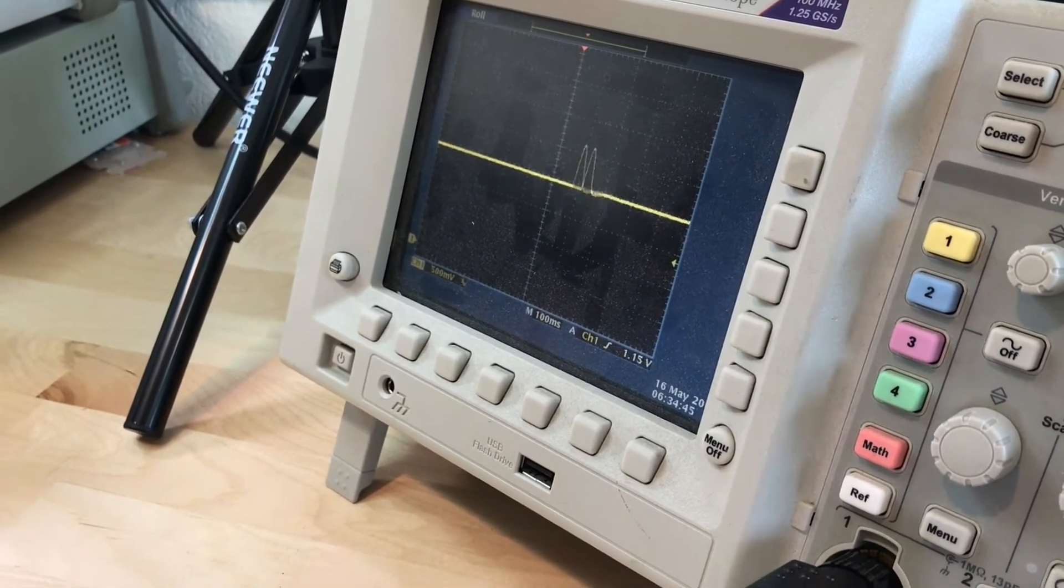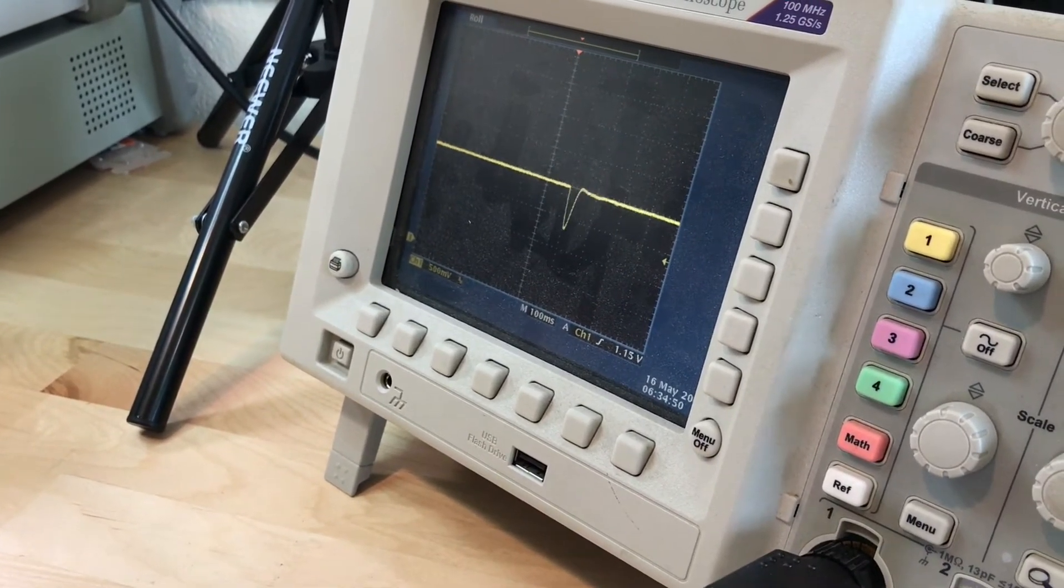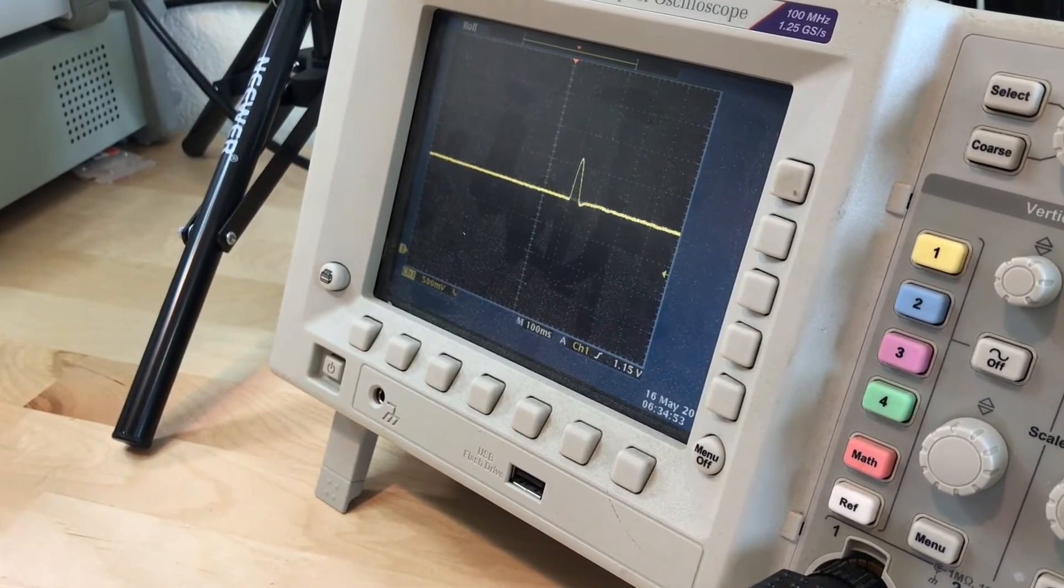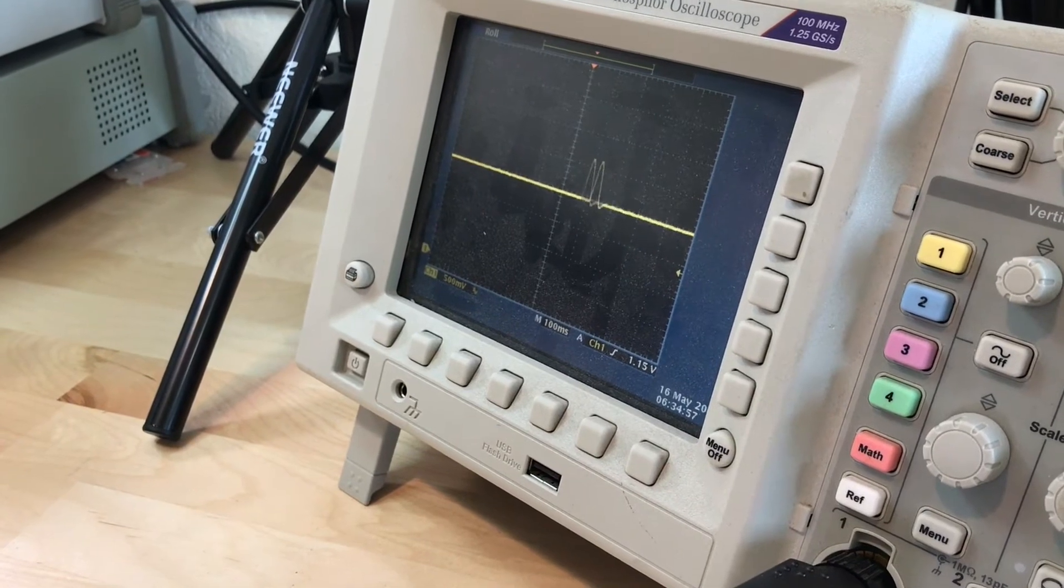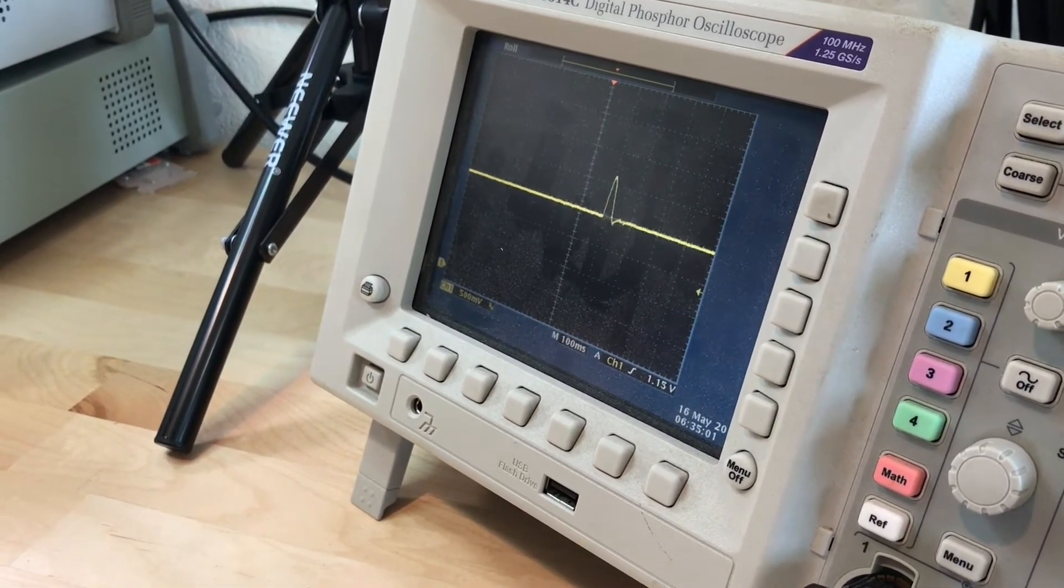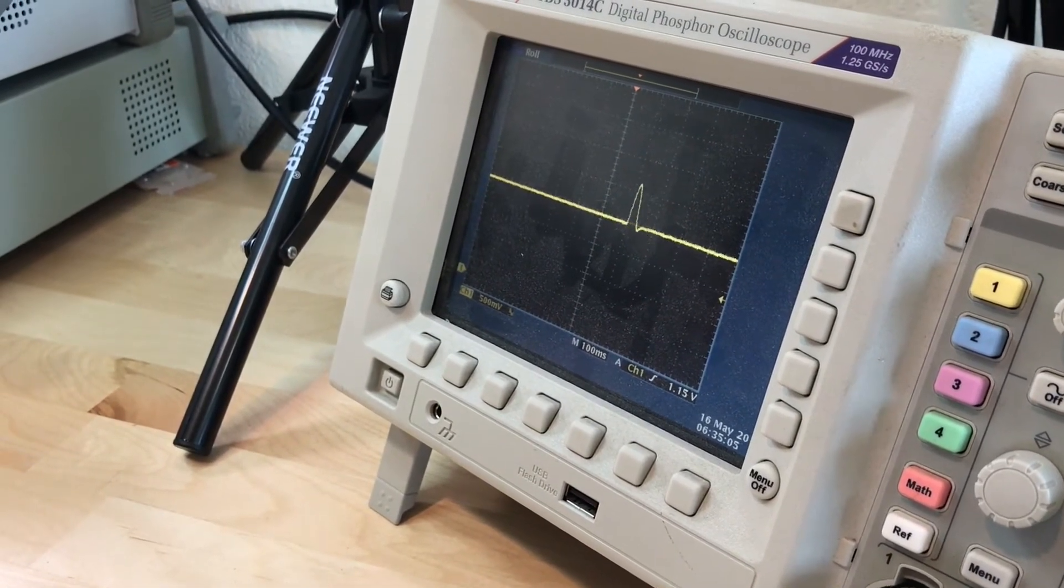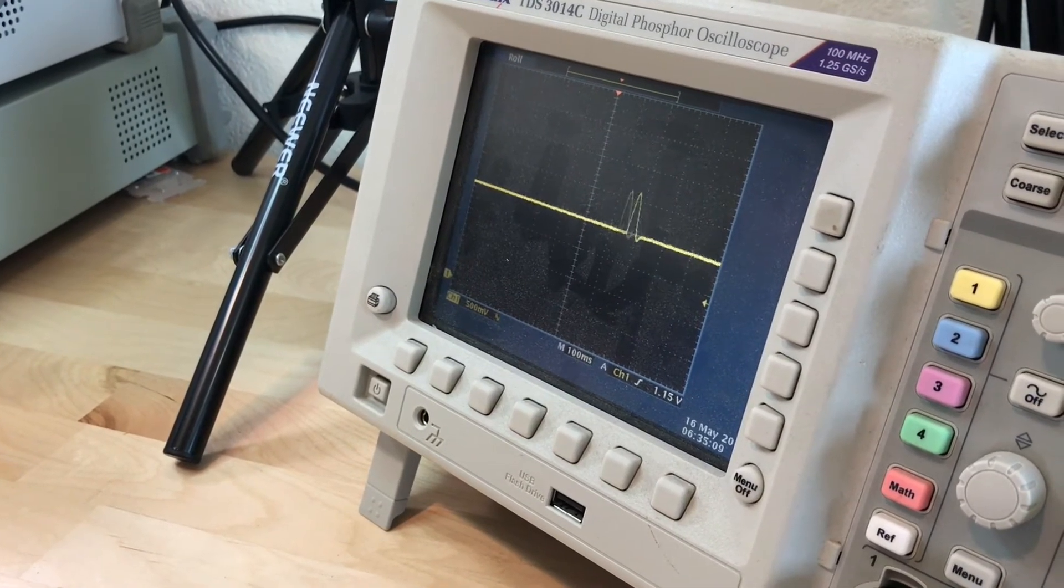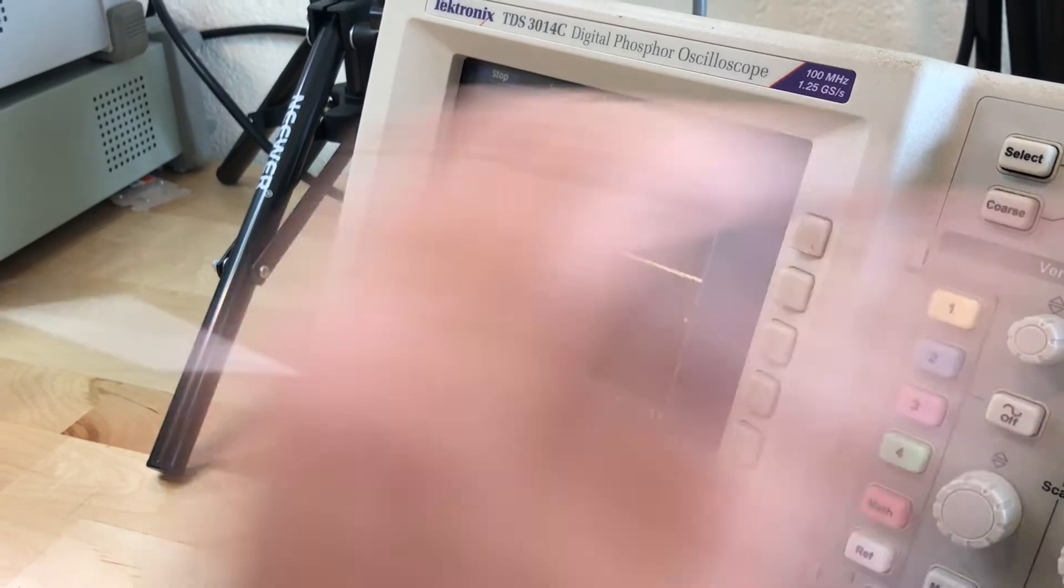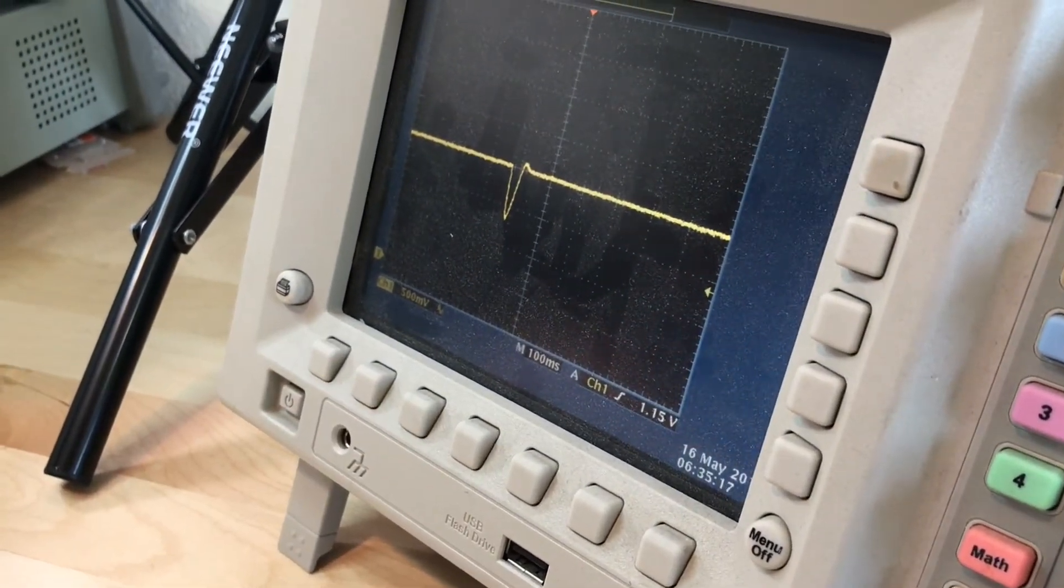Right now I have D at about three o'clock - turned 180 degrees, which is not unheard of when you're doing this. Now turn the P up, and right there seems good with the P and D. P is at one or two o'clock, D is at three o'clock. Now we increase the I just a bit to lower that slope, and you can see that is decently critically damped.